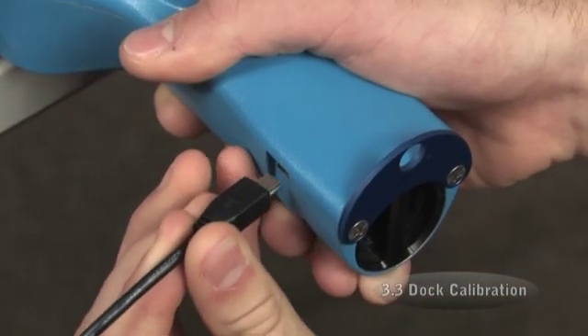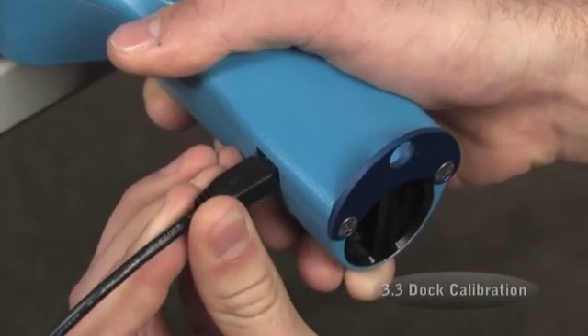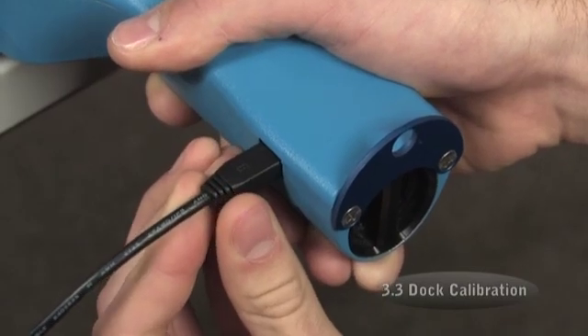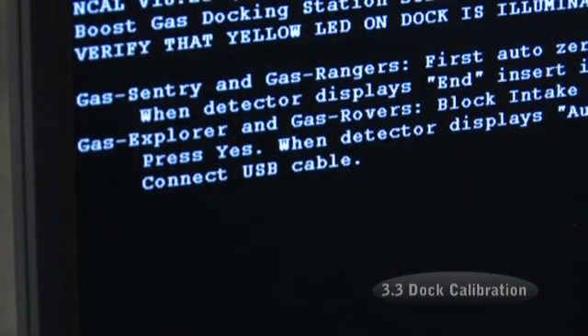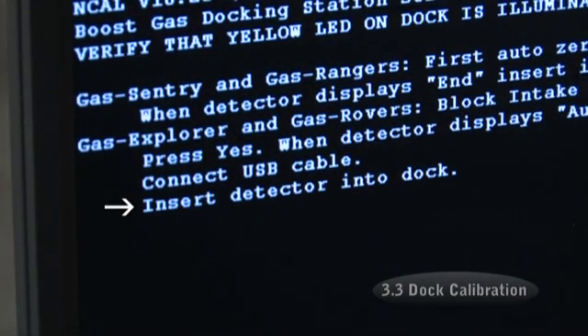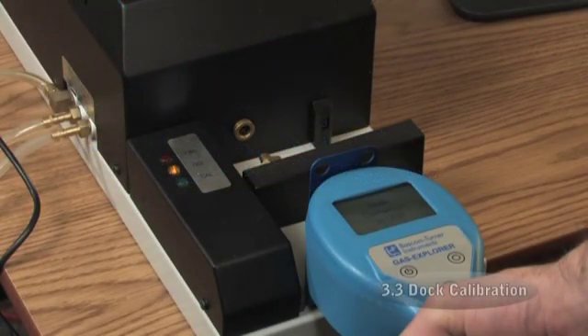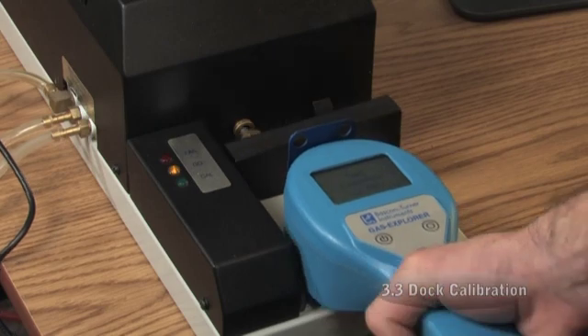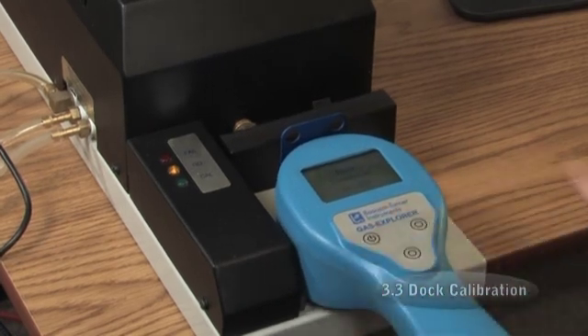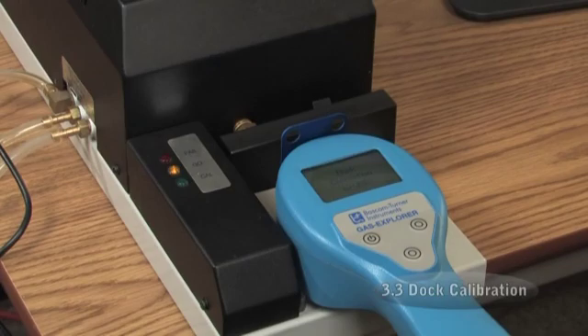Plug the small USB connector into the USB port on the left side of the Explorer handle. Upon connecting the cable to the Explorer, the message Insert Detector into Dock will appear on the screen. It is important to connect the USB cable to the detector before inserting the detector into the dock. Insert the Explorer into the dock by placing the Explorer adapter on the dock and sliding it forward so that the inlet fitting inserts into the port.